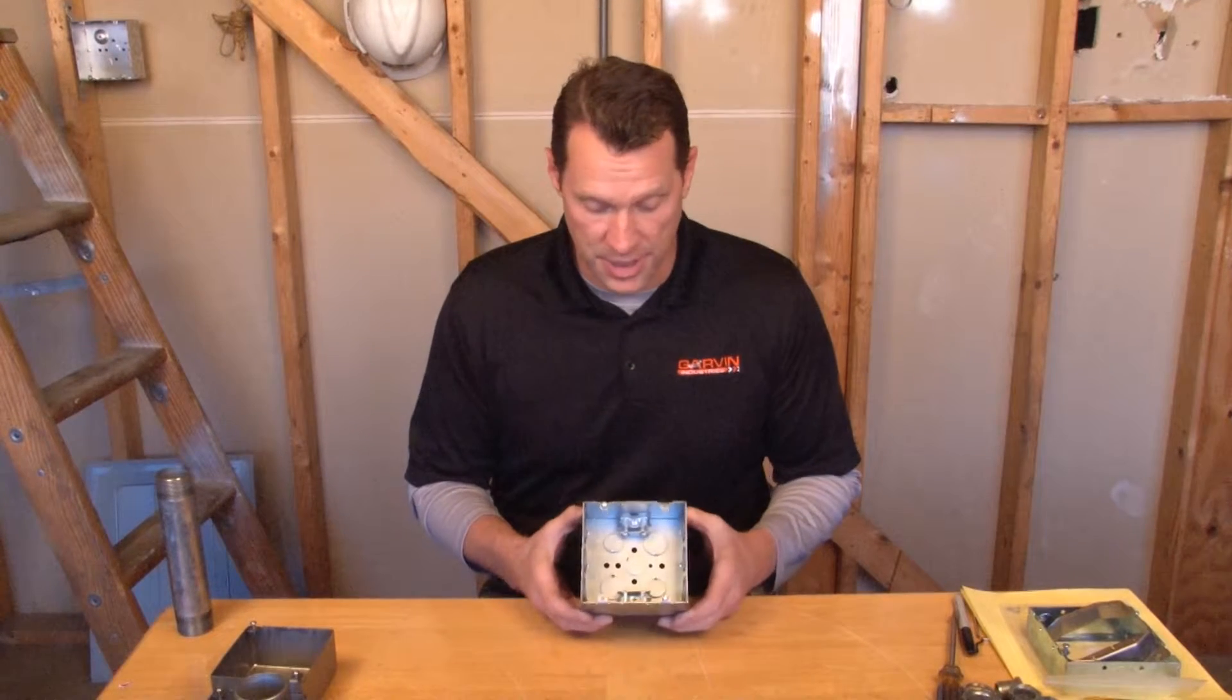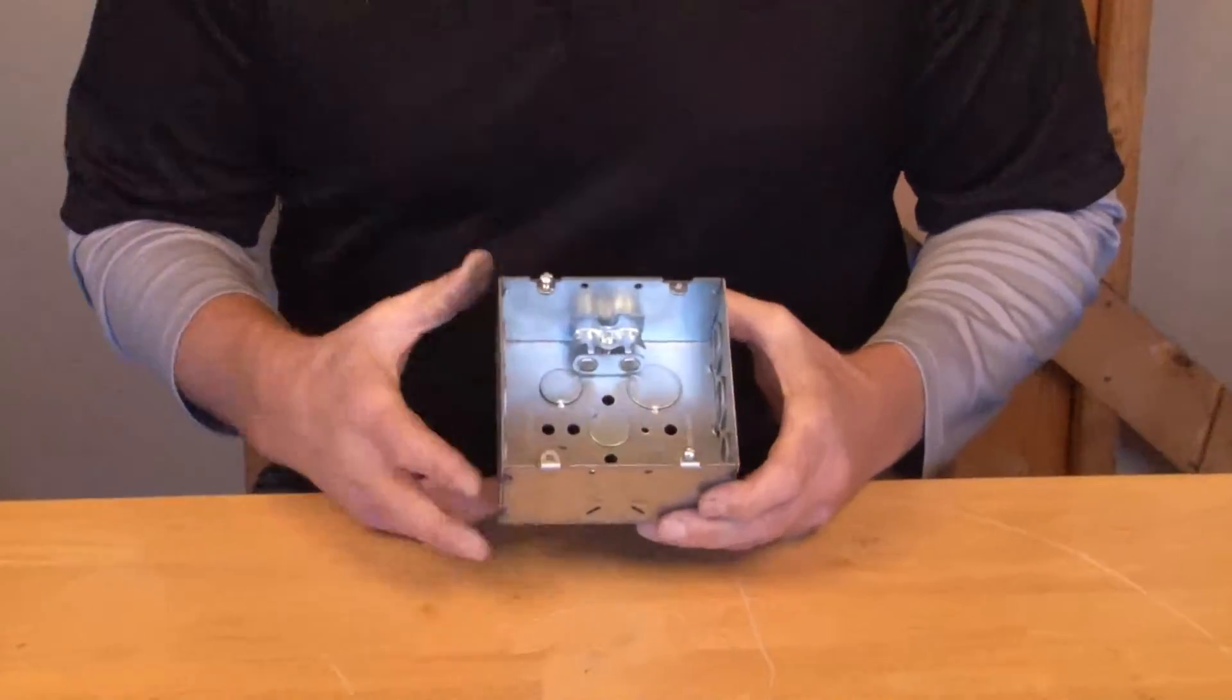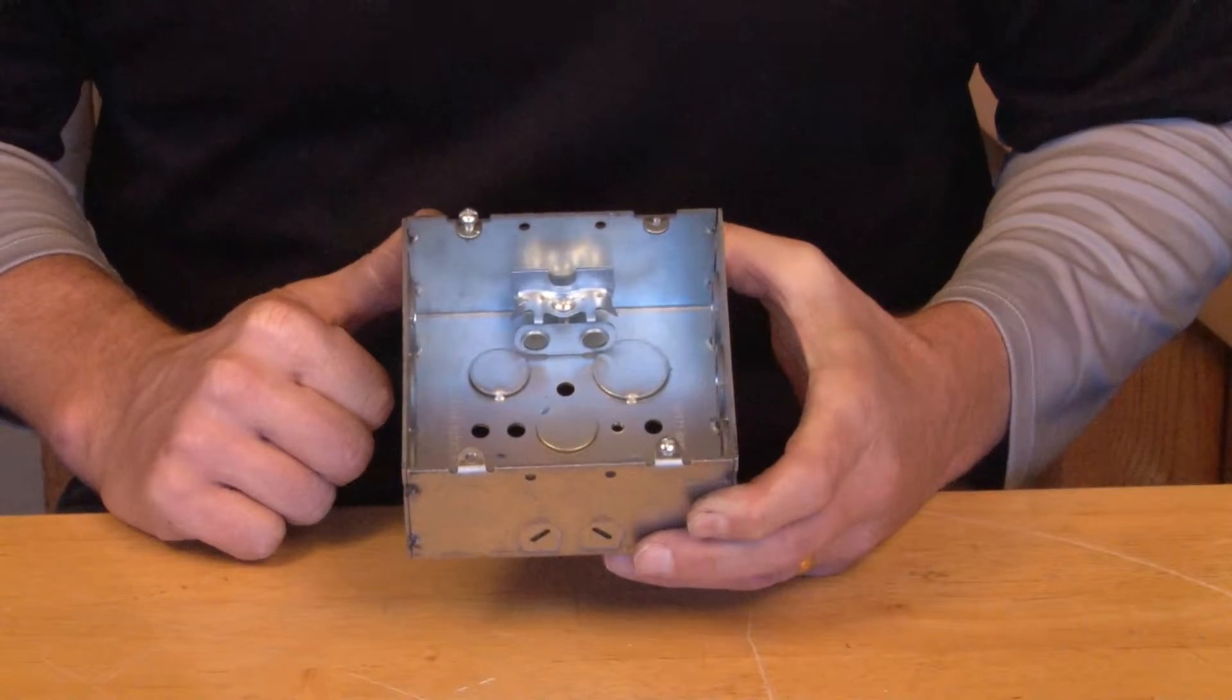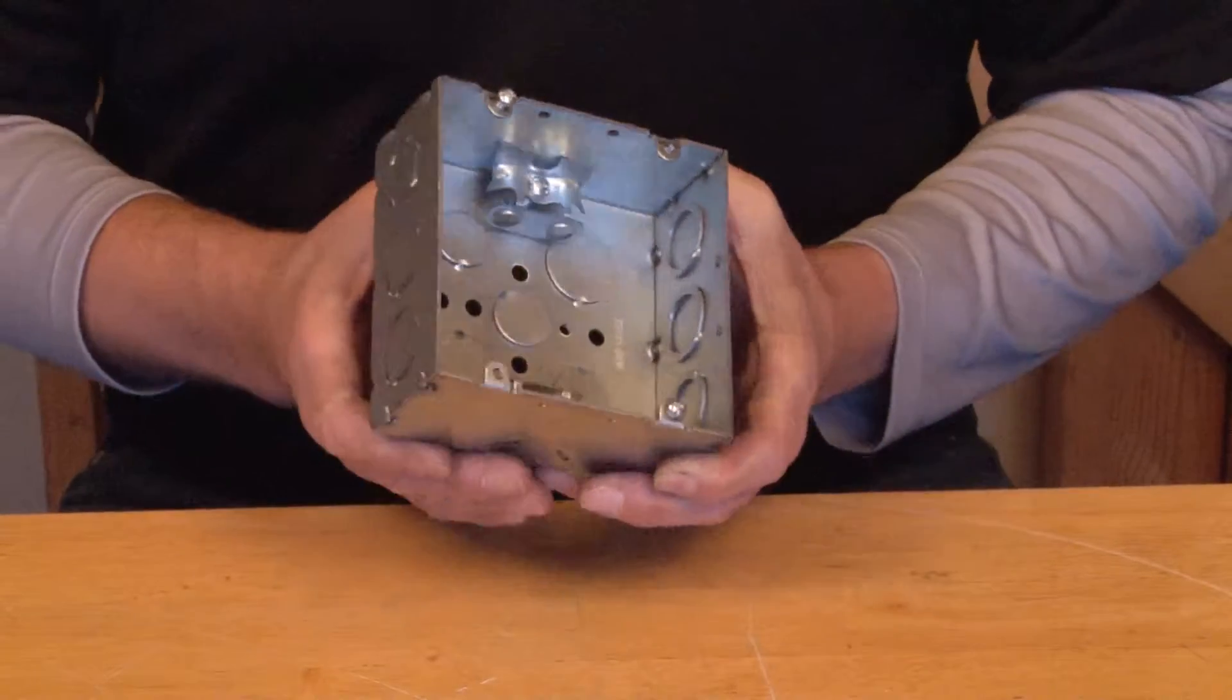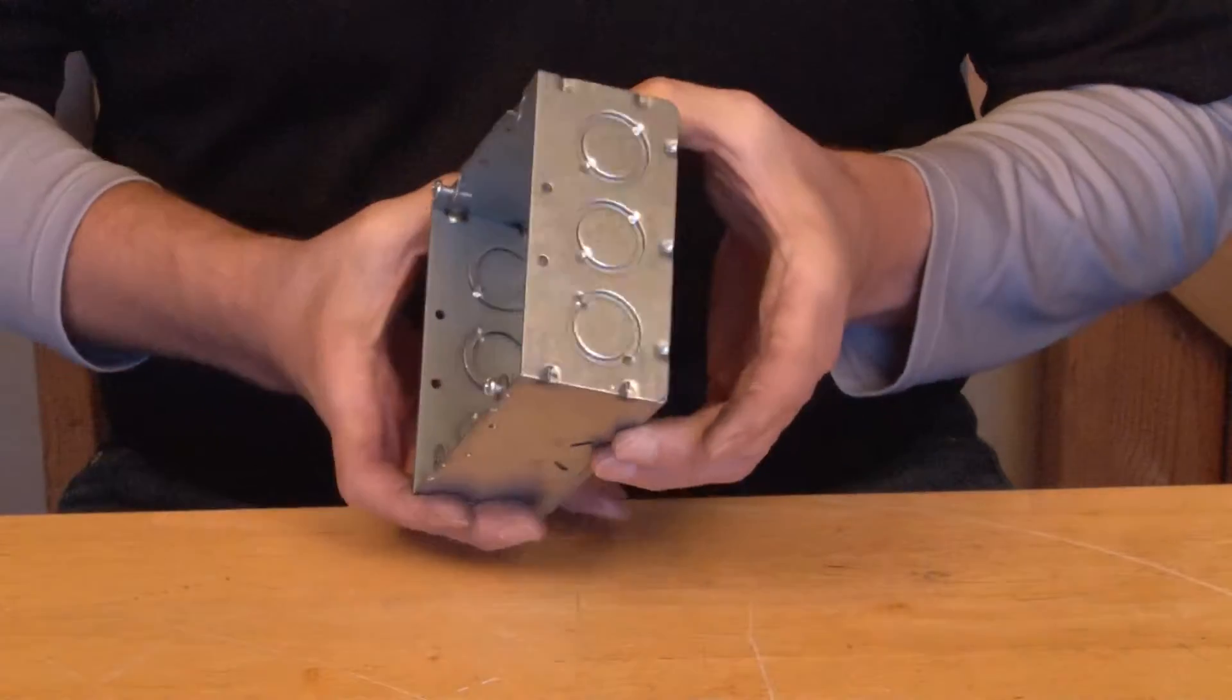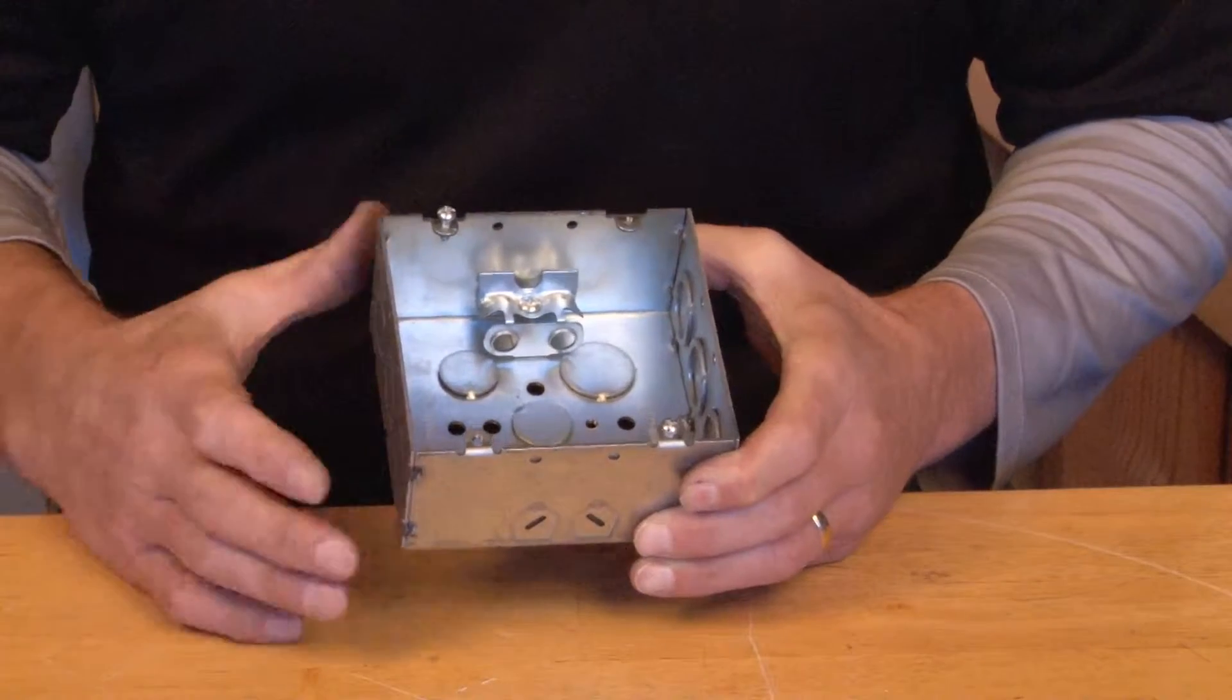72171BXW is a 4 and 11/16 inch electrical junction box that offers four clamps for BX cable. It also offers two sides that have half and three-quarter inch conduit knockouts, as well as conduit knockouts in the bottom of the box.